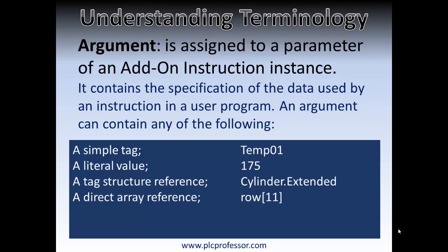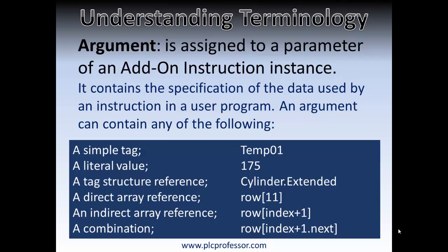It could be a direct array reference, meaning it is referring to element 11 of the tag row — a single dimension array called rows. So if you have a row of cartons, the first carton would be 0, the second 1, and so on up to element 11. It could also be an indirect array reference — if the index was 10, then it would still be row element 11, so you can index this reference with an index value. Or it could be a combination of an indirect array reference and a tag structure reference.